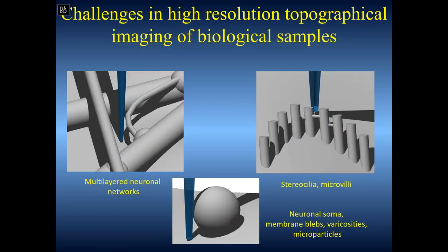The sensor is only at the very tip — and this has advantages. When an atomic force microscope senses any part of the tip, if there is side contact it will be sensed. With SICM the sides are insensitive. This makes it particularly good for elaborated samples which would be practically impossible to image with AFM, but you can image with this technique. You need a special protocol to exploit this ability to get high resolution without artifacts.